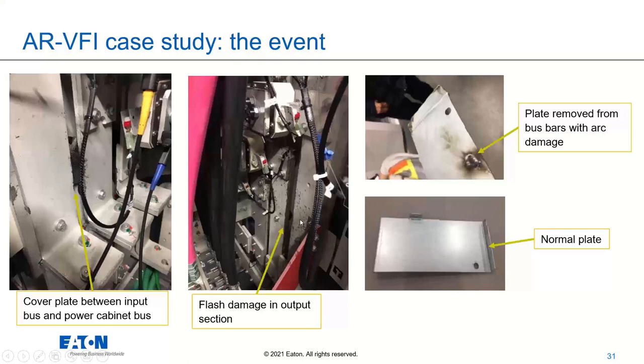Normally, if this was an unprotected secondary, and we didn't have that relaying, we would have vaporized this gear. This would have needed to be completely torn out and reinstalled. And that project schedule, bye-bye project schedule, because now we're having to reorder gear. You're up against lead time walls and all the cost implications that come out of that, versus something that could essentially be removed from the gear, cleaned up a little bit, and you're ready to go. You're back online. Fortunately, no one's hurt. And as I indicated before, not only is no one hurt, but your gear's not hurt. We all care about the human health, but it's really nice when the gear isn't suffering as well.